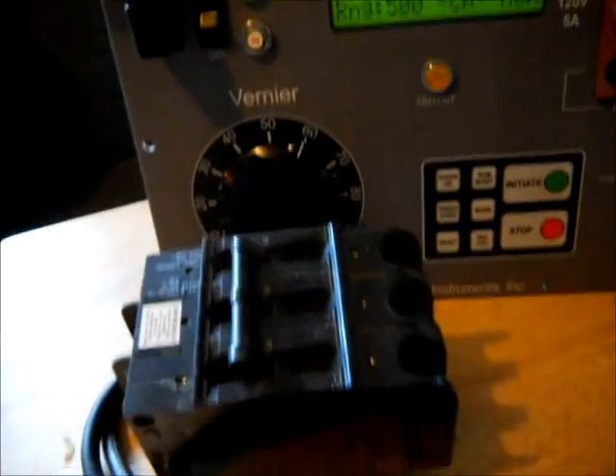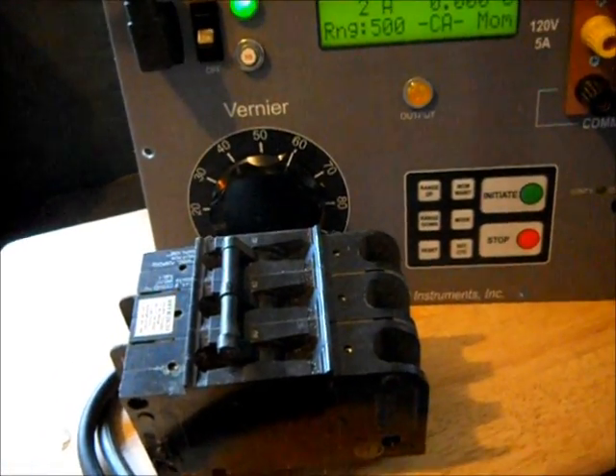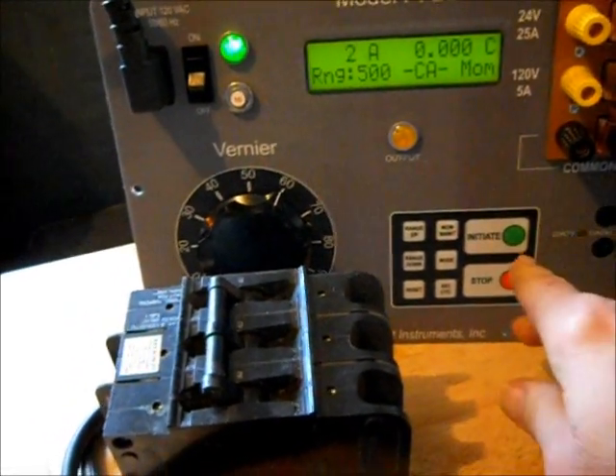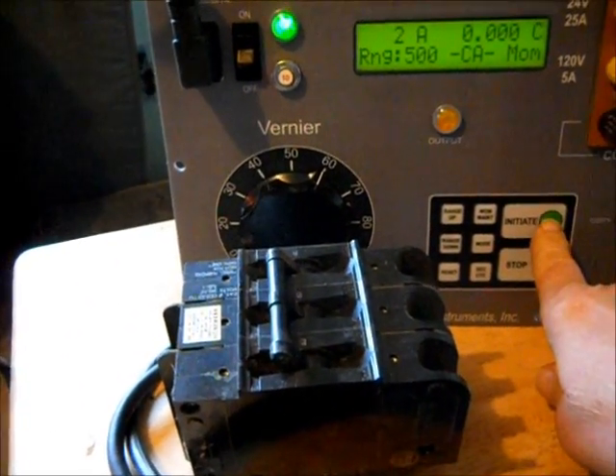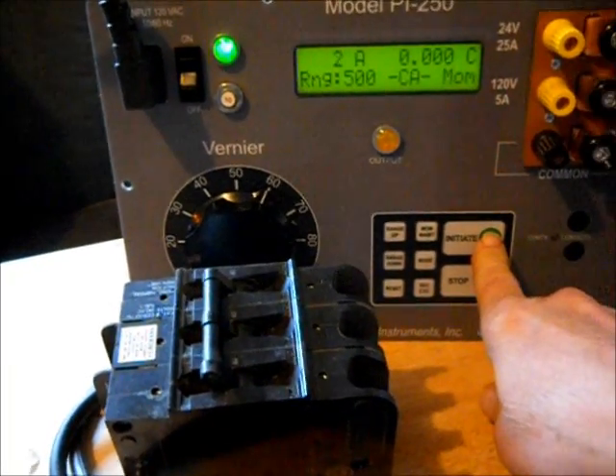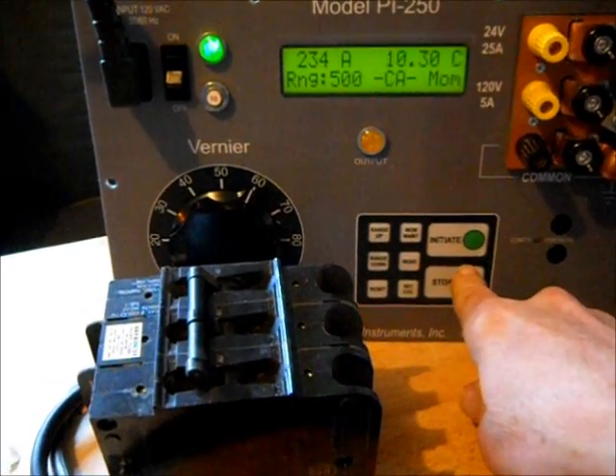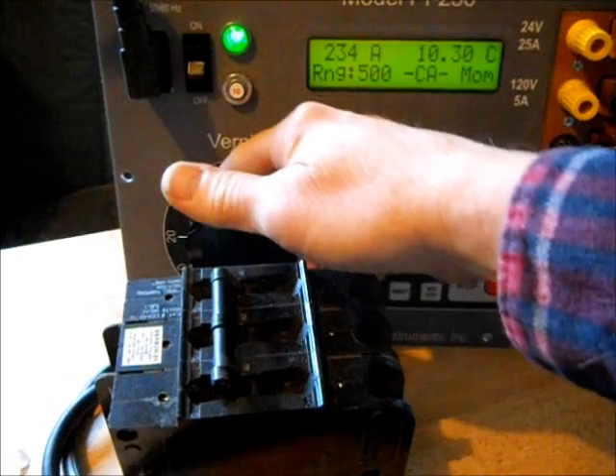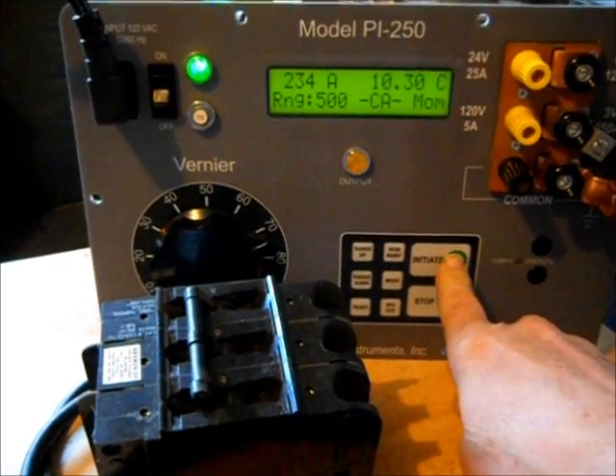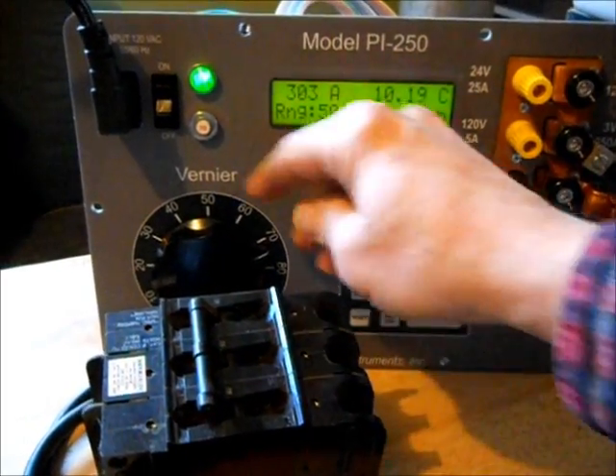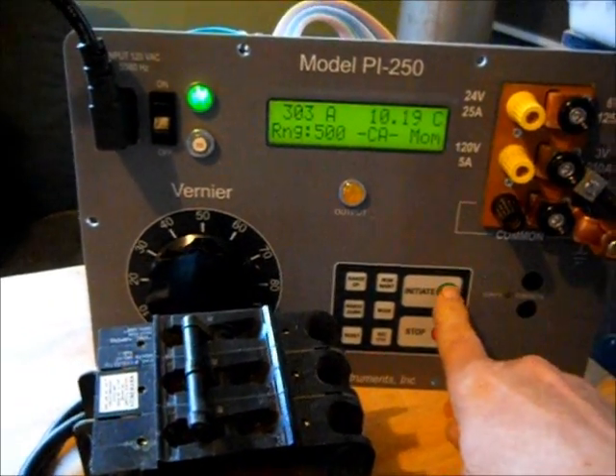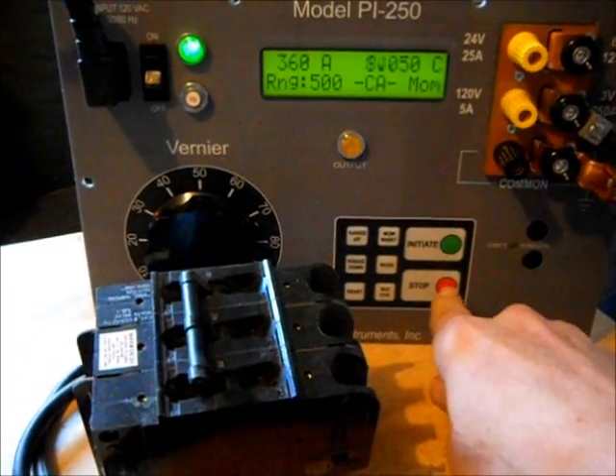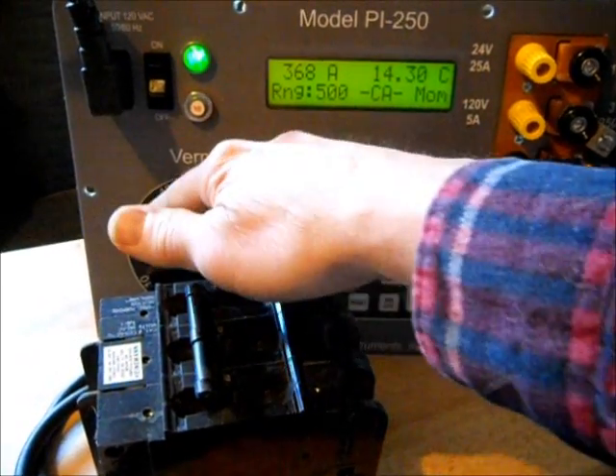Okay, now we'll test for instantaneous trip. I'll have it start at 60%, 234 amps, a bit higher, 303 amps, starts to get a little bit there.